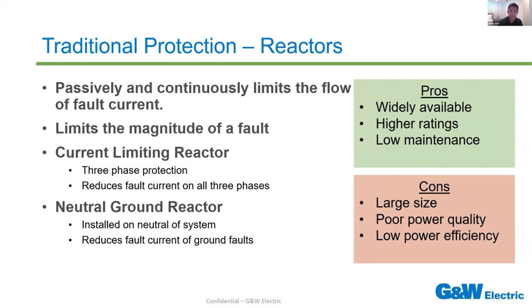Pros, widely available as well. They manage higher ratings than your regular fuses, and again, low maintenance. The con is that they're very large in size. So if you have constraint in real estate, this might not be the solution for that application. Poor power quality due to the impedance that they do introduce some voltage sags into your power system. And again, because of the impedance, you have a low power efficiency, right? So you're gonna incur power losses into your system.